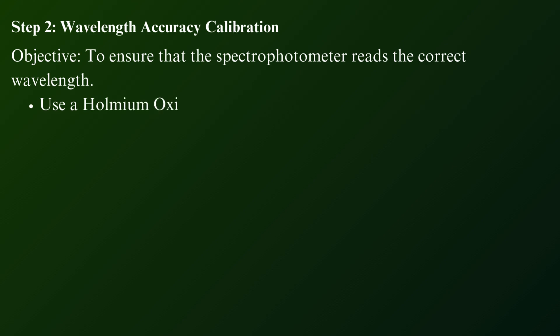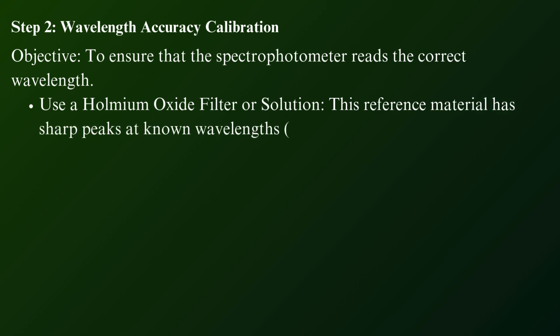Step 2: Wavelength accuracy calibration. Objective: To ensure that the spectrophotometer reads the correct wavelength. Use a holmium oxide filter or solution. This reference material has sharp peaks at known wavelengths: 241.1 nanometers, 287.1 nanometers, 361.5 nanometers.